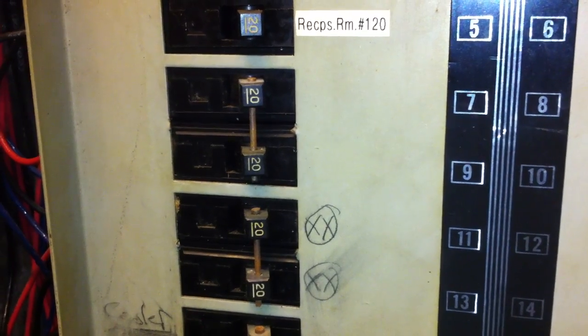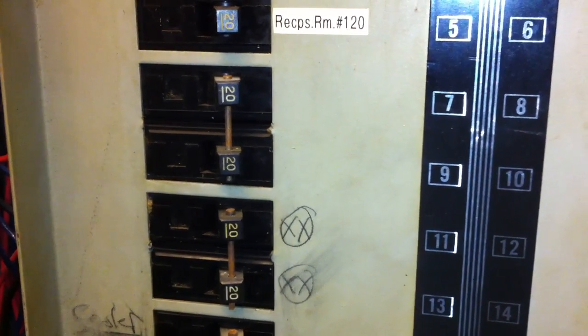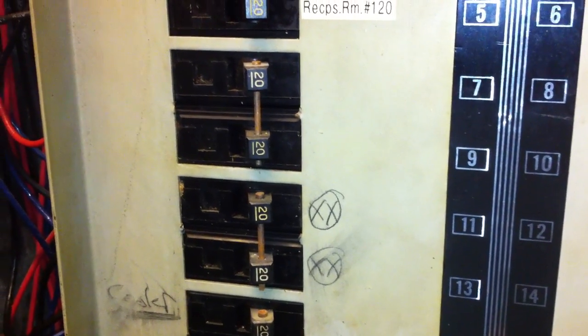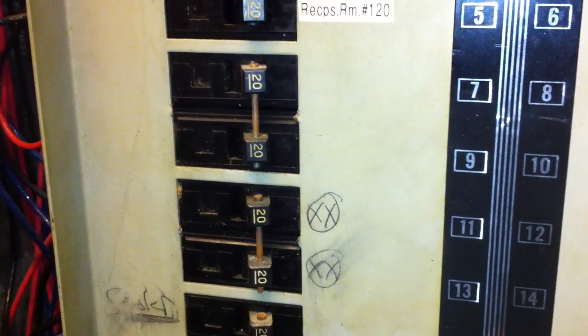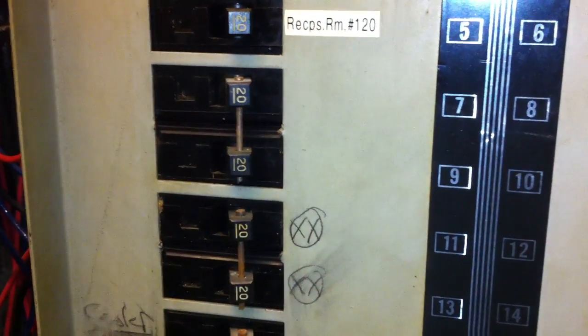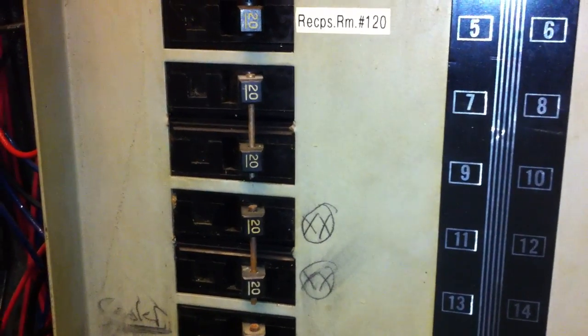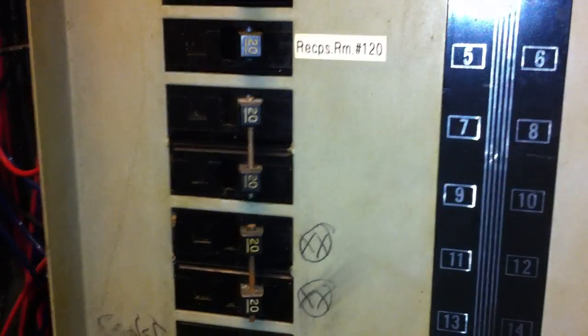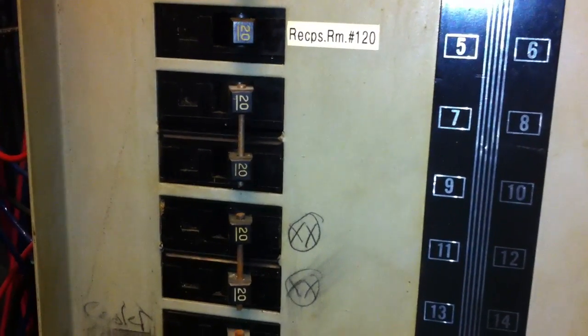Or grounded single phase 120/240 volt circuits. But in any case, identified handle ties need to be used. Nails like this are not identified as circuit breaker handle ties. This is Russell Blank, NEC consultant for EC&M magazine.